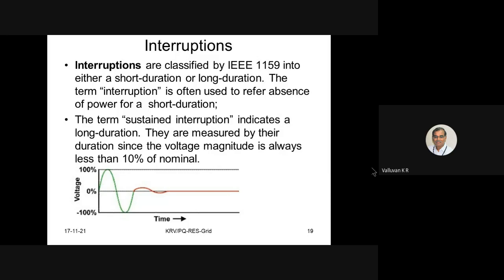At homes or even in colleges, we have large UPSs. So in the computer center, even if the mains power fails, the UPS takes over, so we don't see any difference. But this is only a small thing. See, a power failure in hospitals can cause loss of life. If equipment working on mains power loses power for 1 second or 0.5 second, the patient will die. Power failure in industries can create production loss for 2-3 hours. There are a few industries where sustained power is required. Once the power fails, about 10 hours of production is lost, and it takes another 10 hours to restart the production. So there, interruptions are not tolerated at all.